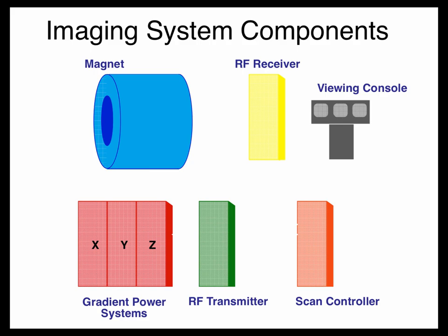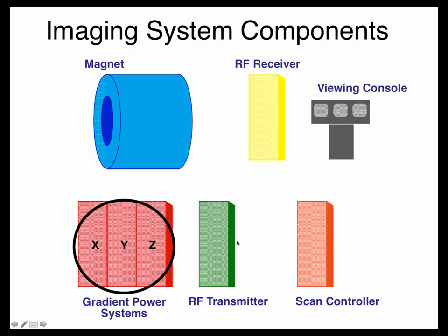I'm not going to go too much into that other than saying that we no longer need local gradient coils for echoplanar imaging. We still could use local gradient coils for doing high performance diffusion imaging, but I'm not going to get into that right now. Right now we have much more beefed up gradient amplifiers, and that allows us to do extremely high speed imaging with whole bore echoplanar imaging scanners.